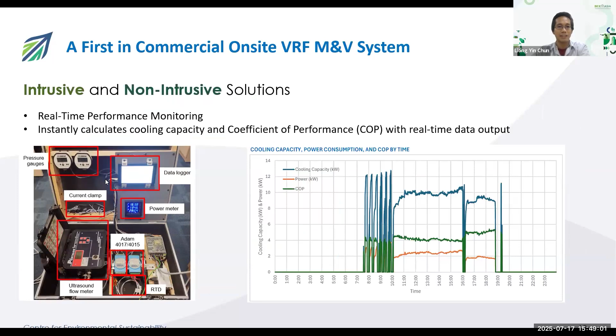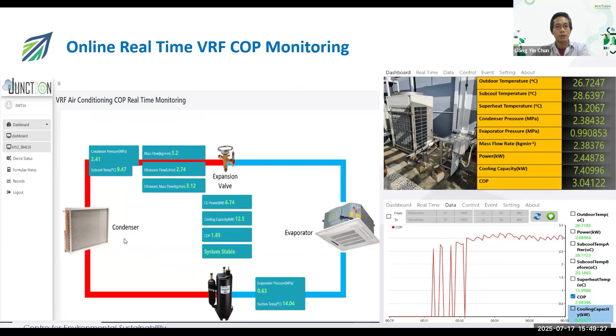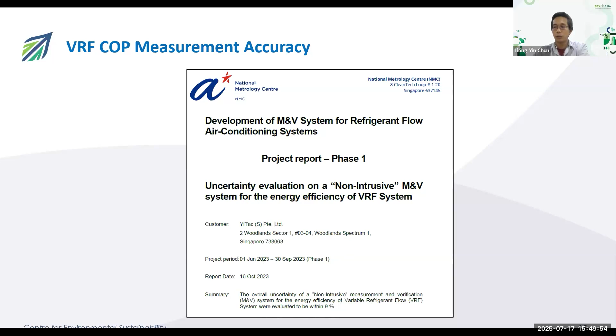And if we have the measurements, just one step further, we have the cloud system. So we also built in the cloud system, so now we can measure the COP value of the on-site VRF system, and the end user can log into the portal and see the COP value online in real time. So these are the verifications that we did with A-STAR, where you can see that the efficiency of the variable refrigerant flow system was evaluated to be within 9%. It's a non-intrusive system, so we don't need to cut the pipe. We just have the ultrasound tap on it, and then we can tell the COP in real time.